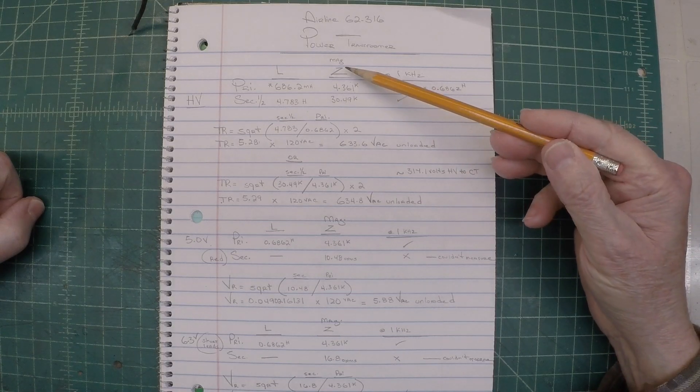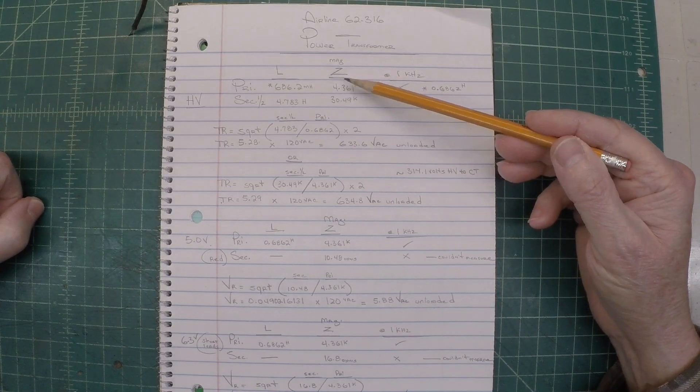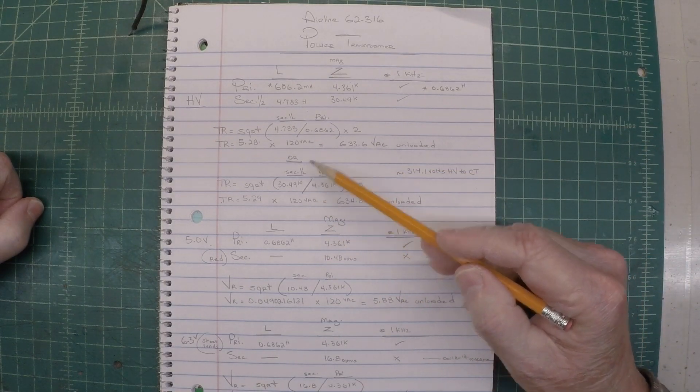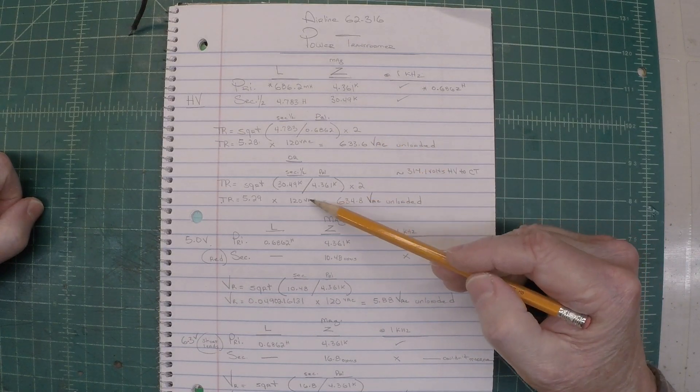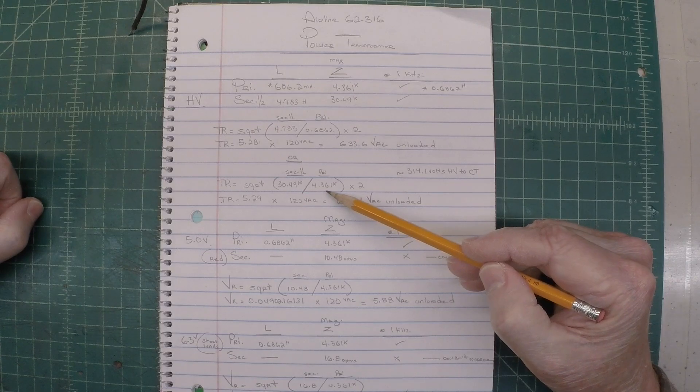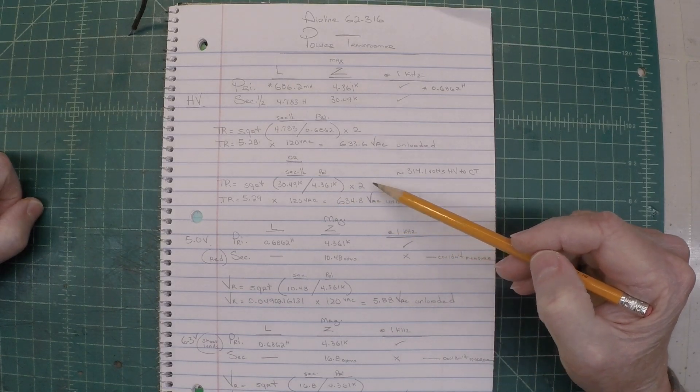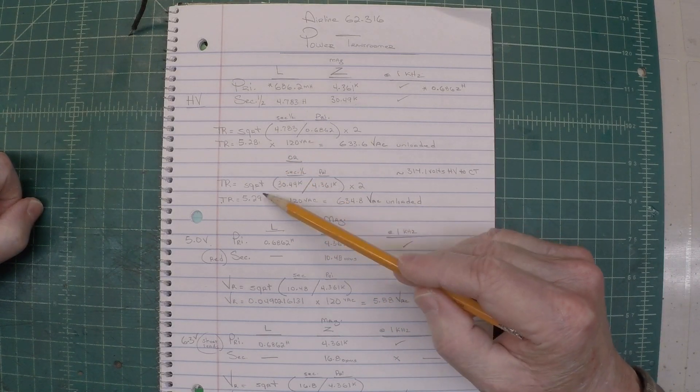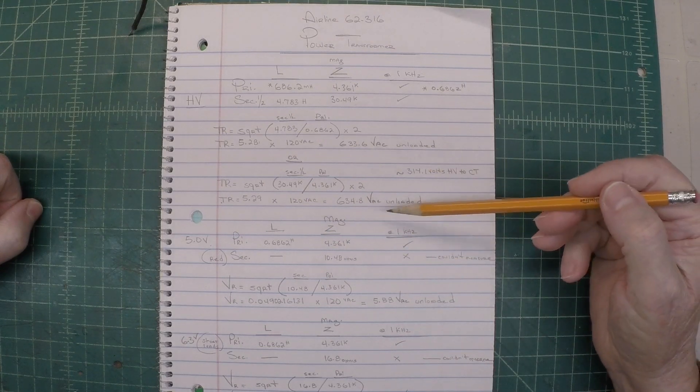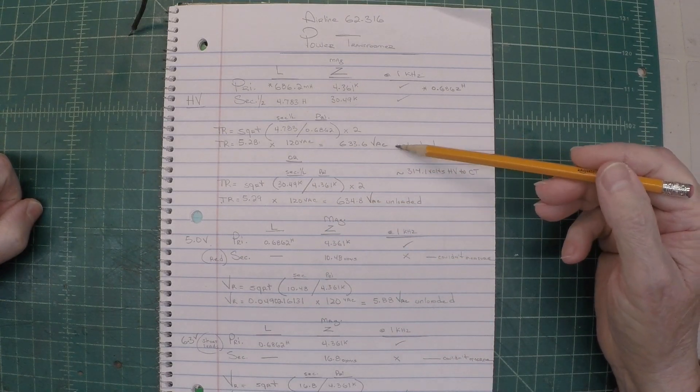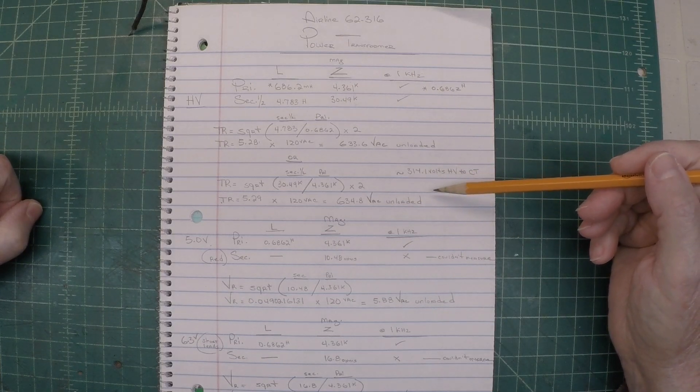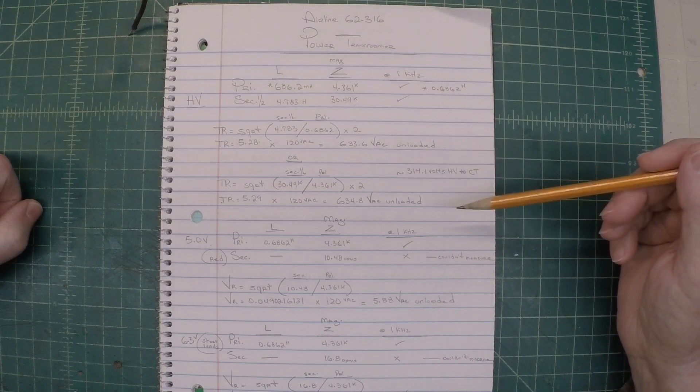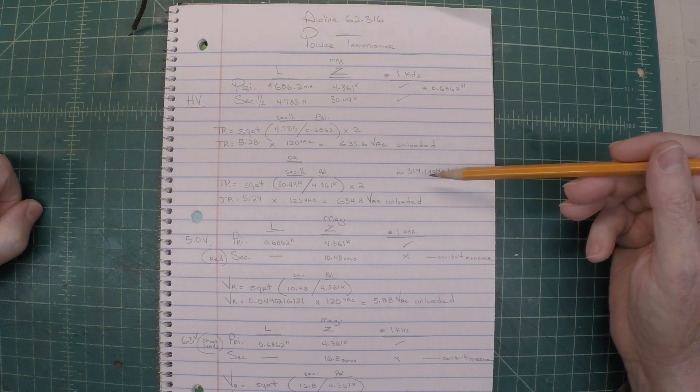I can also use the magnitude of Z impedance. Do the math the same way. Take the secondary, one half of that number, the 30.49 K, divided by 4361 times 2. You can see the numbers are extremely close. Turns ratio was 5.28. Now we're 5.29 times 120 comes out to 634.8. So an average between those around 317 volts high voltage from the center tap back to each winding is what I should see once the transformer is under power.